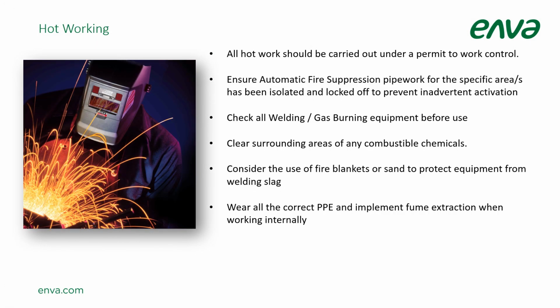Hot working. All hot work should be carried out under a permit to work control. Ensure automatic fire suppression pipework for the specific area has been isolated and locked off to prevent inadvertent activation. Check all welding or gas burning equipment before use. Clear surrounding areas of any combustible chemicals. Consider the use of fire blankets or sand to protect equipment from welding slag. Wear all the correct PPE and implement fume extraction when working internally.